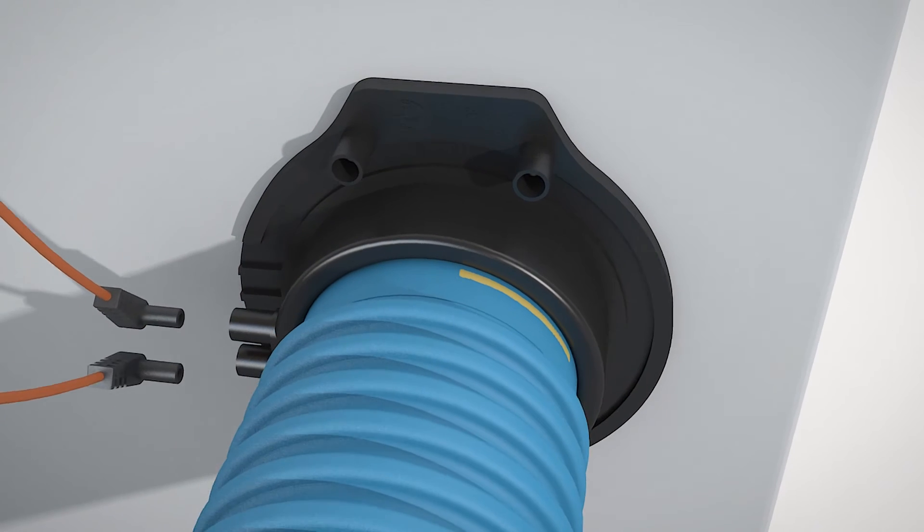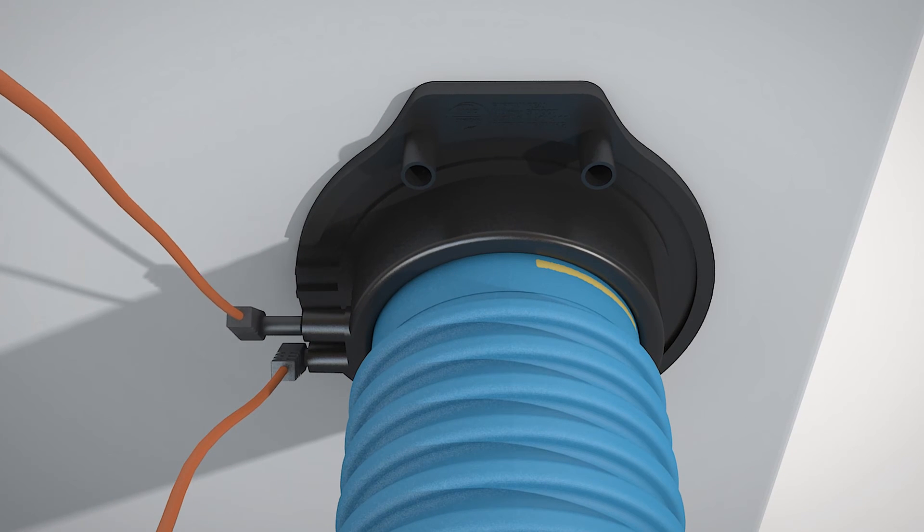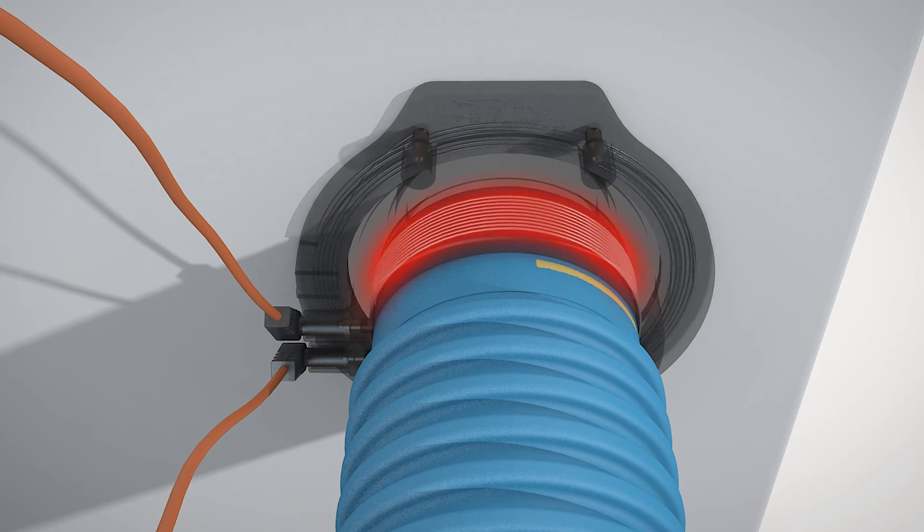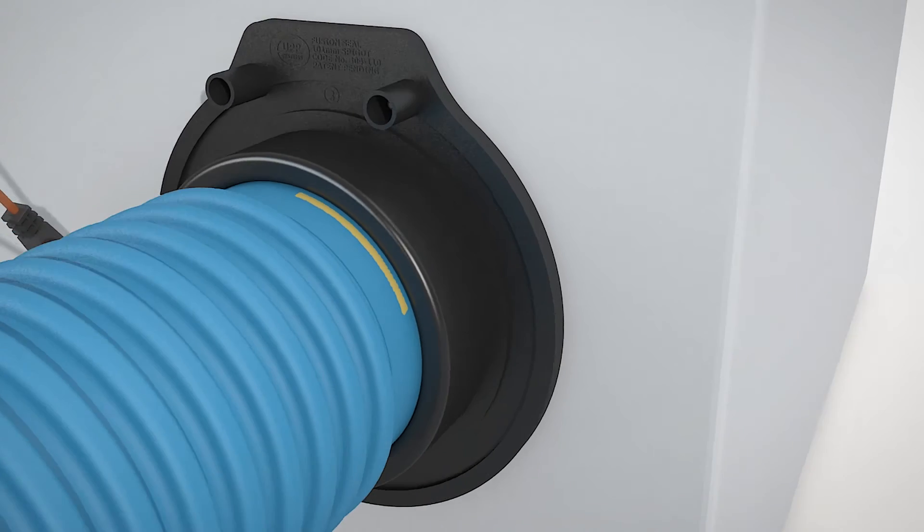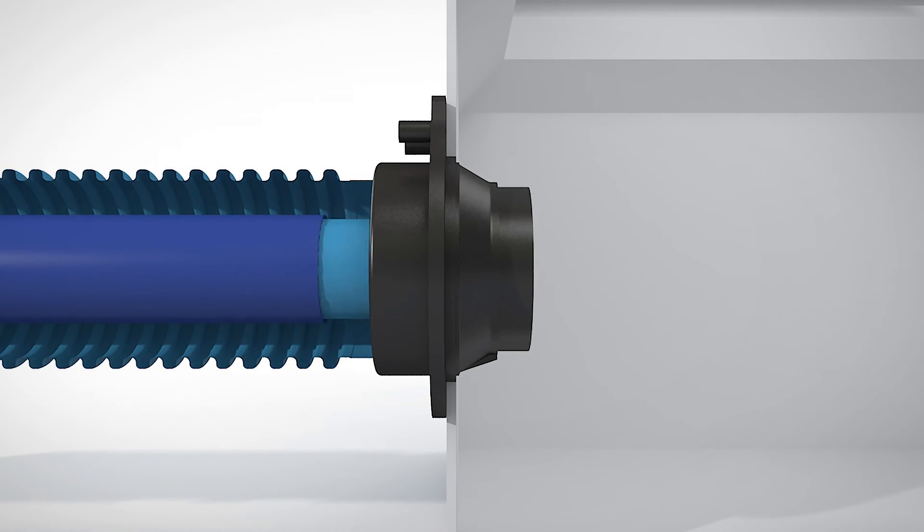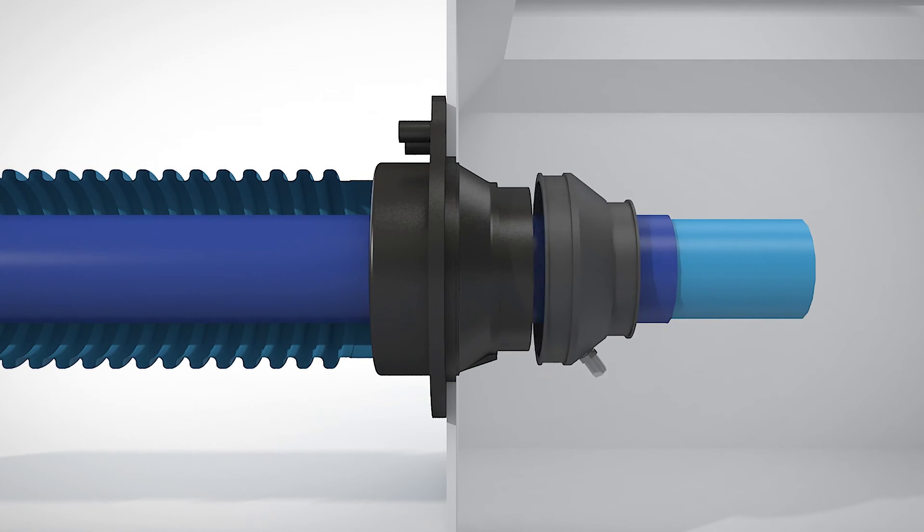Once the welding process is completed, you'll wait 20 minutes for it to cool. Then you install your XP pipe, install the reducer and band clamps, torque it to the complete specifications, and your system is complete.